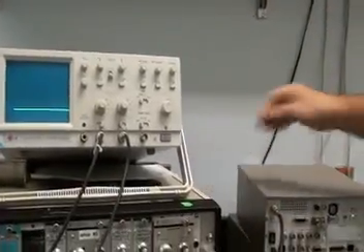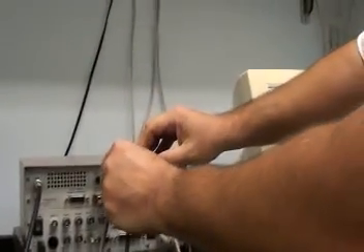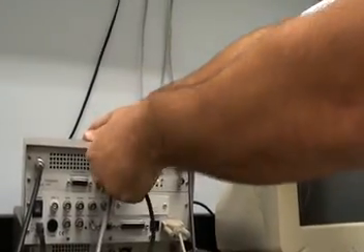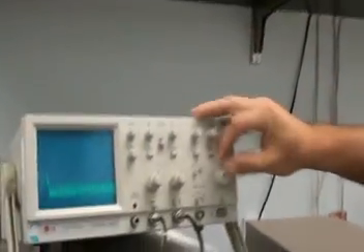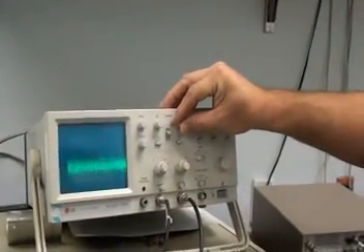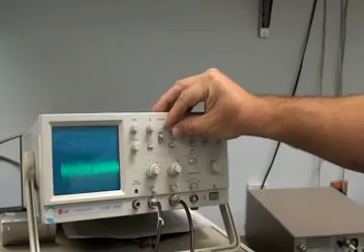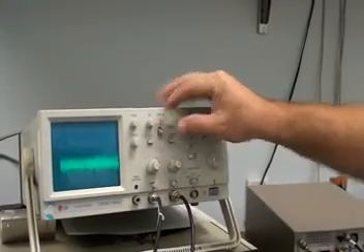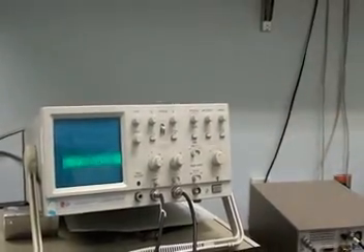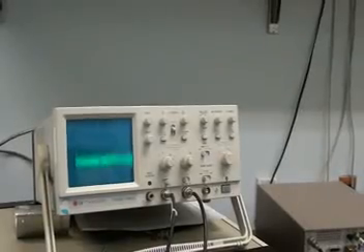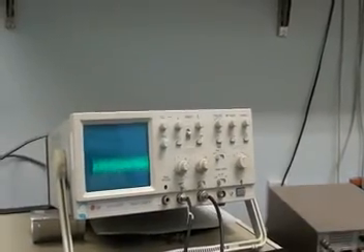Now if you have access to an oscilloscope, you can take a BNC to your oscilloscope and look at the amp out. You will see a large noise — probably about 400 millivolts of noise. This will show that the preamplifier is working, and you are ready to proceed with applying bias to the crystal.